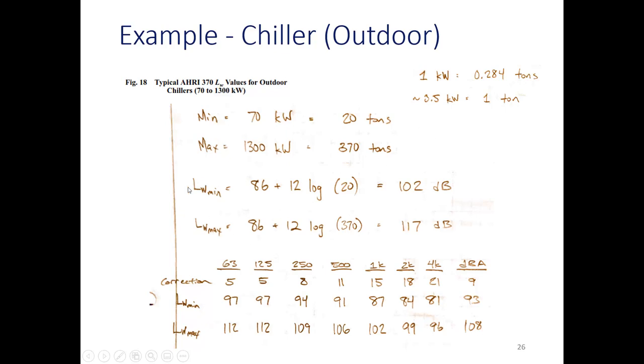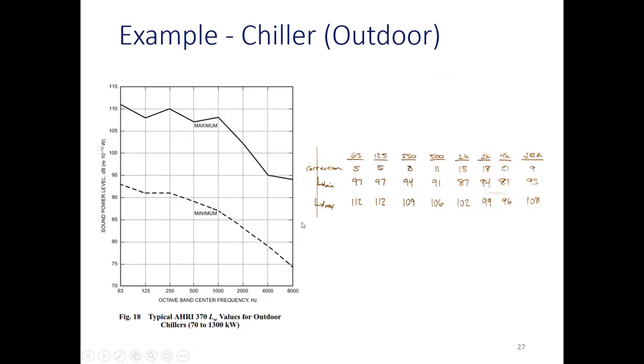But for the sound, we convert these using this conversion factor. The 70 becomes 20 tons, the 1300 becomes 370 tons. So this is a pretty big unit. A lot of the units are fairly small, and this is a pretty big unit. They're covering a pretty wide range. But we plug those in. The minimum overall is 102. The maximum overall is 117. If we apply those corrections, for each one of these we're subtracting this from this and this, and we get this. Now we have this table here, that's essentially our solution.